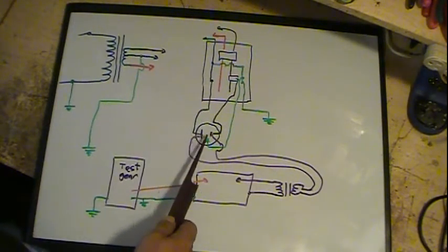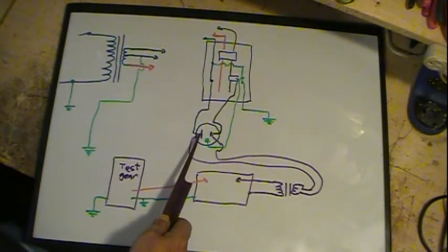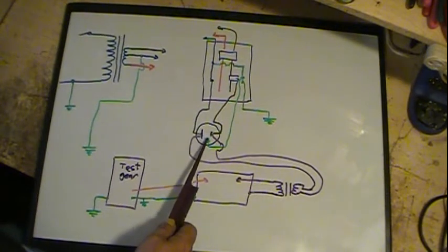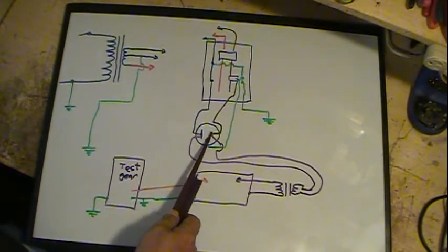So the ground connects up to one spot in the box and that hooks to the ground wire that goes to your eight-foot ground rod that's in your yard someplace by your house. They also make a jumper across either through the box or directly across to the neutral to make sure it stays grounded and stays neutral. So these two actually should have the same potential, no volts between them. If you ever measure them and they do have low voltage between them, there's a problem. The only voltage you should see is you measure from hot to neutral, hot to ground.